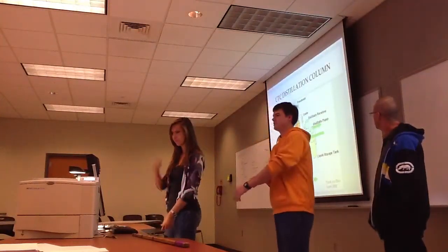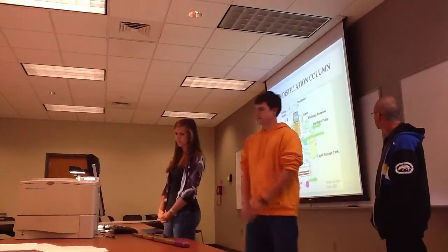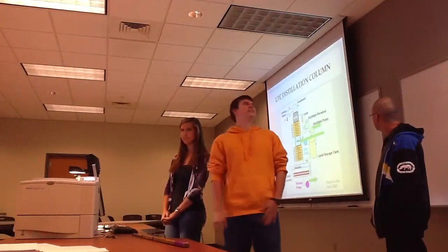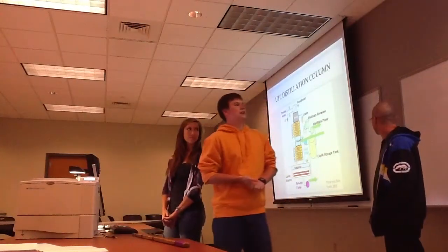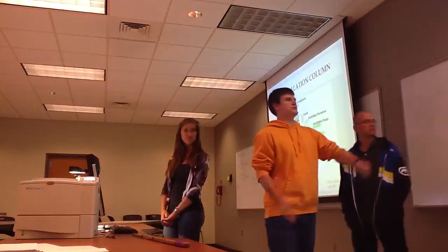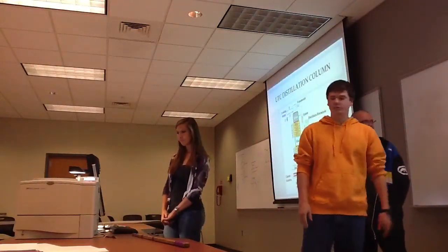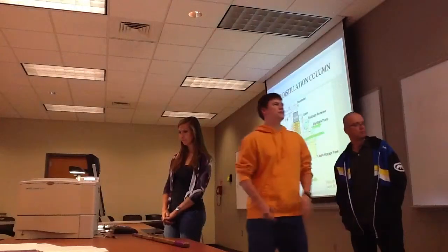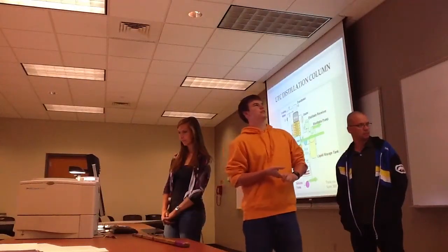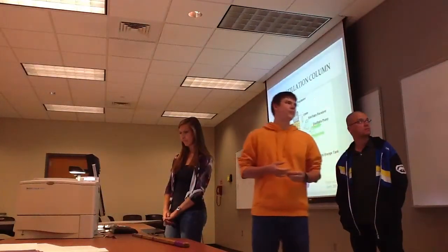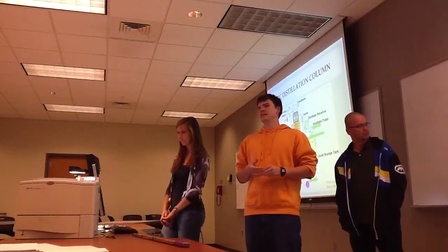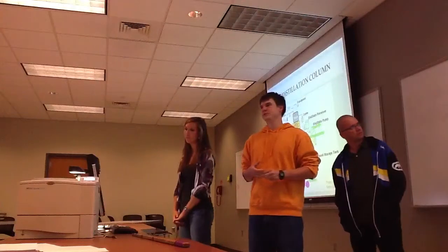This is our distillation column. Thanks to Team Blue from 2002 who made it. It's set up with our reboiler at the bottom, and we have 12 trays with the feed in the center and the reflux and the condenser at the top. We currently run it using batch distillation, but it can be set up to run continuous.